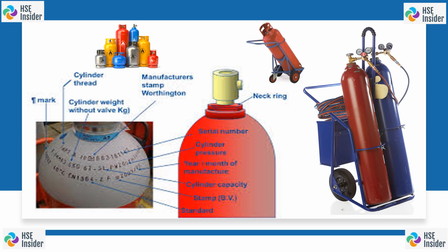Then come to the next requirement on the valve. Valves to be fitted to gas cylinders shall comply with the specifications. For industrial gas cylinders, it should meet the requirement of Indian Standard IS 3224.